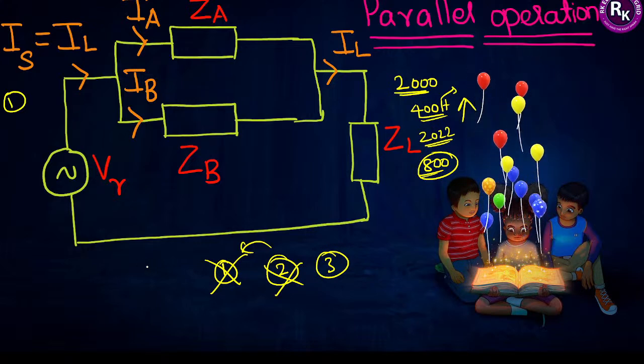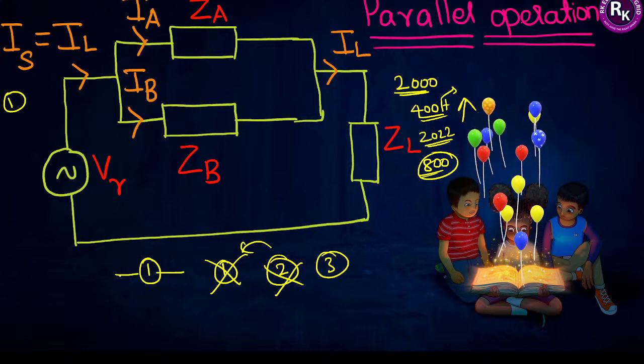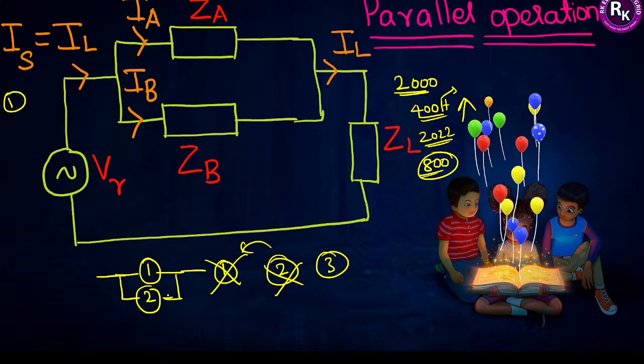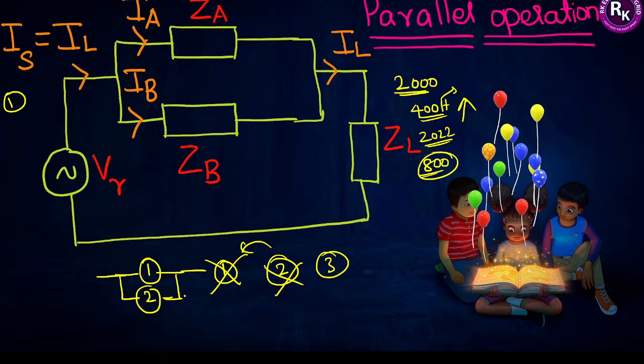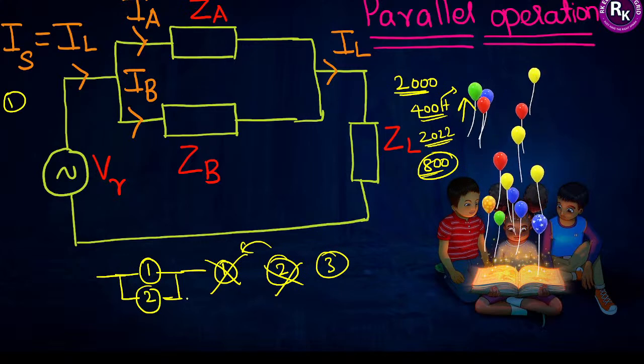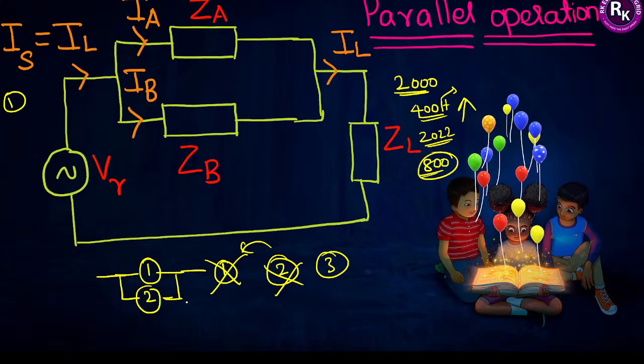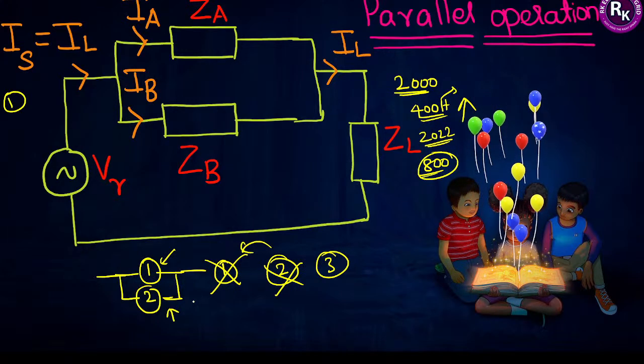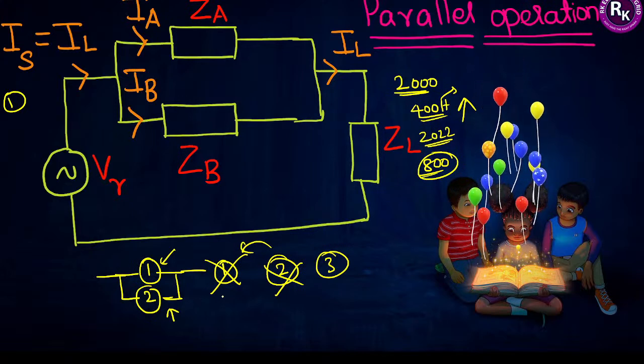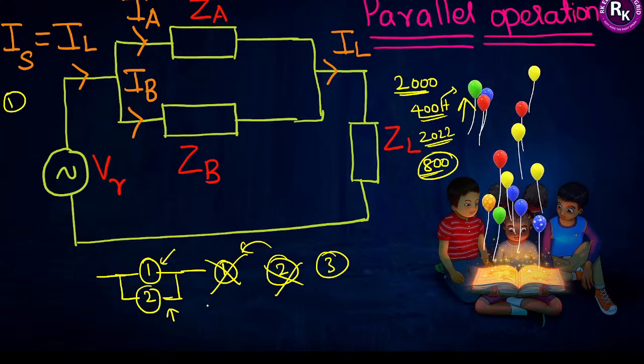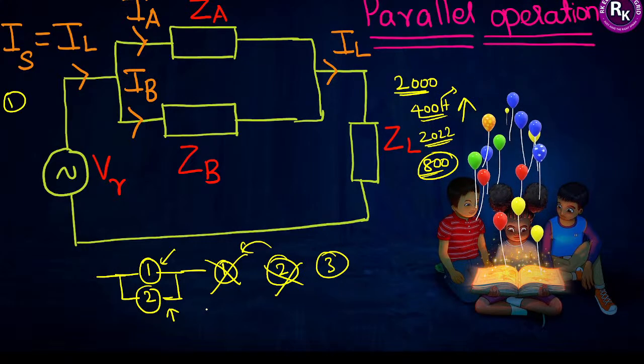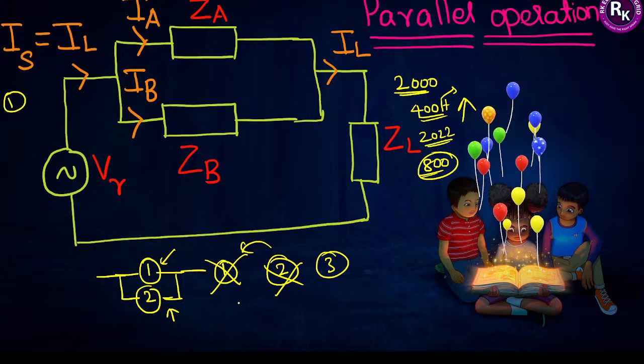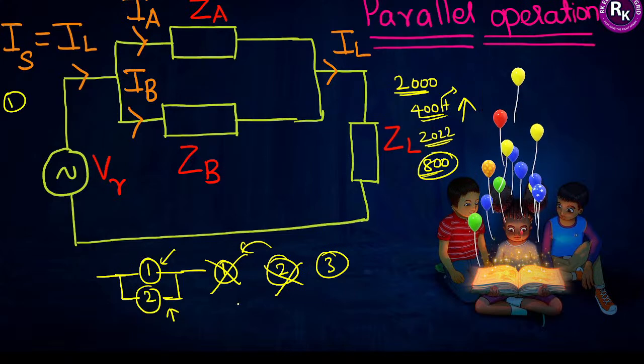What people started doing is connecting transformers in parallel circuits. An already-existing transformer continues to operate, and along with it, in parallel, we bring one more transformer. In a parallel connection, voltage remains the same. The biggest advantage is the existing transformer is still there and the incoming transformer is brought just to meet the additional demand. There is no need to replace the existing one; it is economical and easy to transport, since we manufacture only the transformer sized for the additional load.